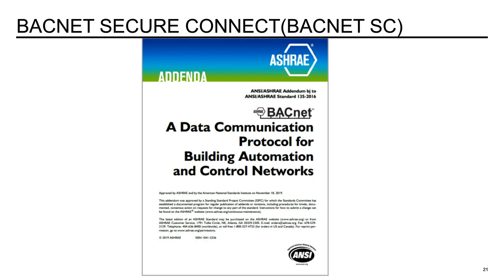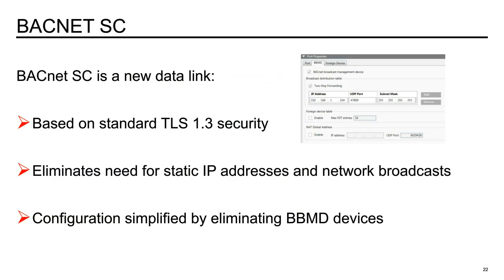So what is BACnet SC? BACnet SC is a new data link that eliminates many of the security concerns owners, facility managers, and IT professionals have with BACnet networks today. BACnet SC provides the means to create secure communications between building automation devices across the cloud and within facilities.